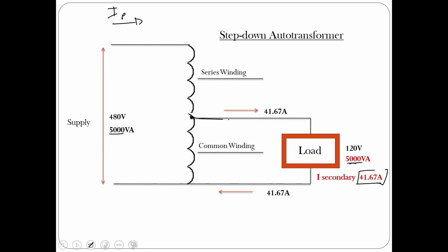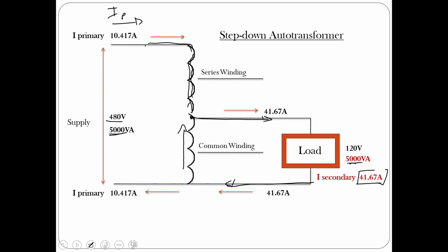So that means out of this junction, 41.67 amps flows to the load, and it's got a return back right here. Okay. Now if we calculate the primary current, 5000 VA divided by 480 volts, we're going to have 10.417 amps coming in. So comes in, there's only one path, and it's to go through this winding right here, which is our series winding. So that ends up being the I of the series. And then, so that 10.417 comes down, 41.7 splits, takes off, 41.67 comes back, so we have to have current coming back to that junction. Goes in, and then 41.67 leaves. And 10.417 has to return. So this conductor has to be the same current as this one coming back. So what's the difference between 41.67 and 10.417? The difference between is going to be 31.25.